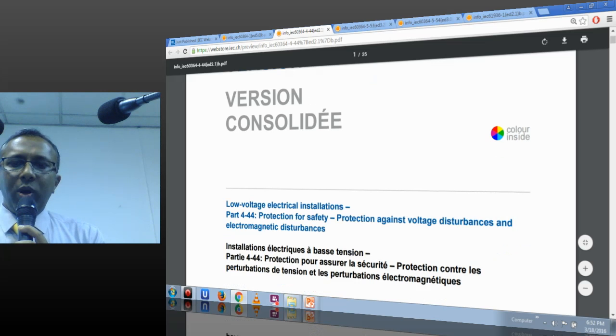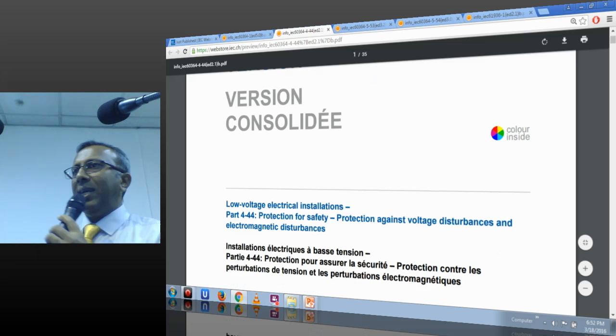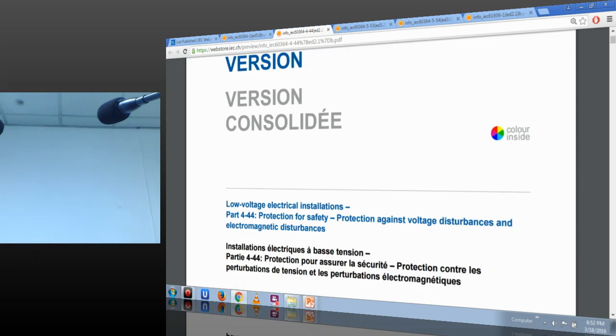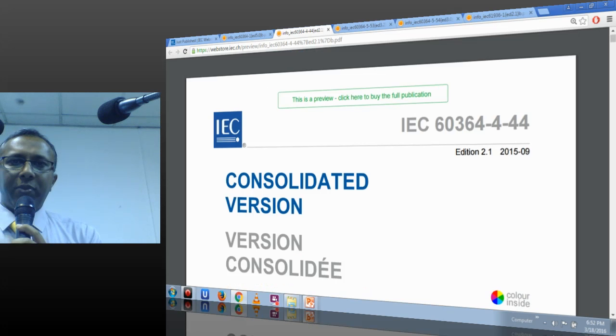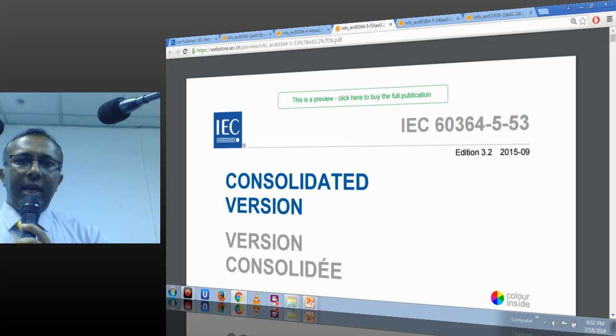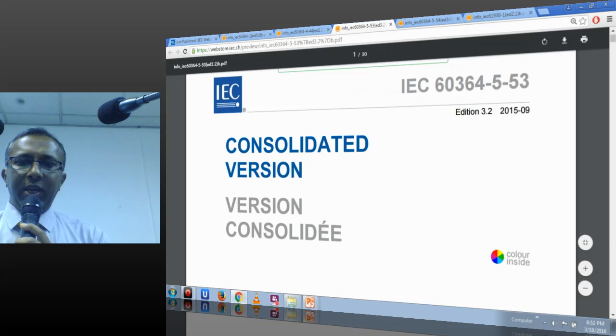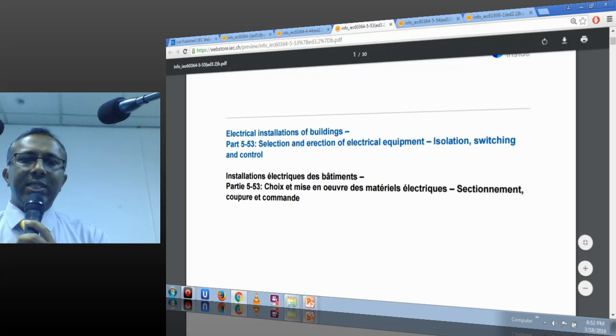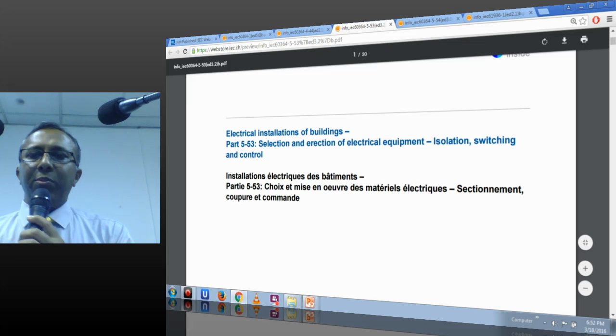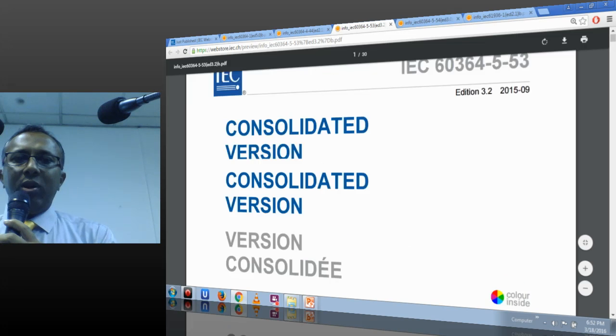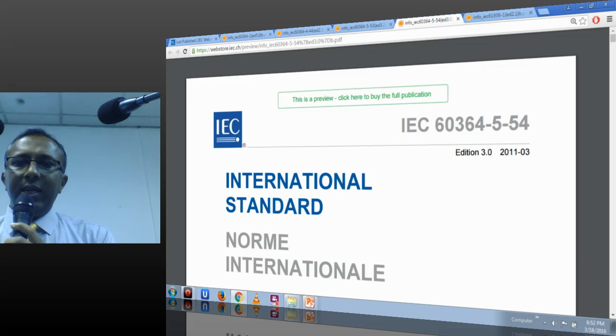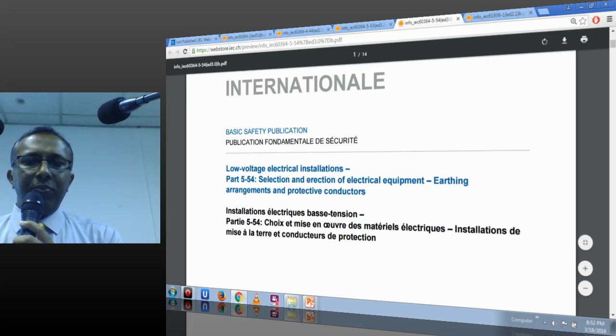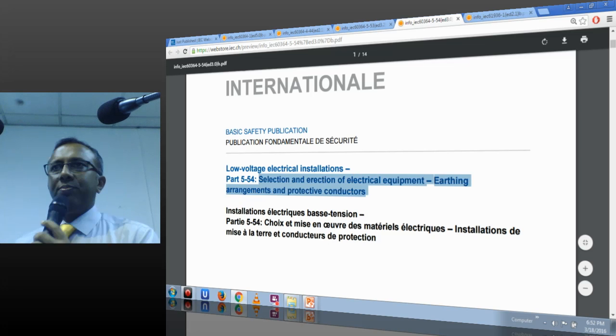Protection against voltage disturbances and electromagnetic disturbances in the electrical installation of a particular building is explained in this particular standard, 60364 444, and 60364 553. It talks about what kind of protection devices, and the selection and erection of electrical equipment for isolation, switching and control. This standard also needs to be considered. 60364 554: selection and erection of electrical equipment, earthing arrangement and protective conductors.